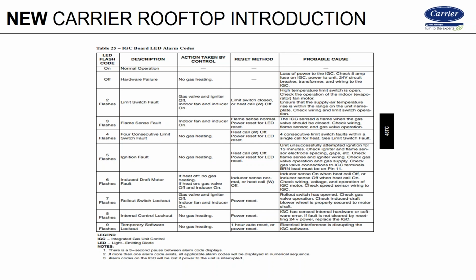And then on the back end, on the cool down cycle, if we trip at 60 seconds cool down, then it's going to extend it out 15 seconds like before. Start extending that cool down cycle out. So indoor fan modification, when that used to be broadcasted and listed, that's what it was. It wasn't that the fan was being modified, it's the timing that was being modified. So that's 1. For 2, anytime you have a fault code 2, that means you got a limit switch fault. So either that limit on the fan housing or the limit on the side of the panel, if either one of those trip, you get a fault code 2.